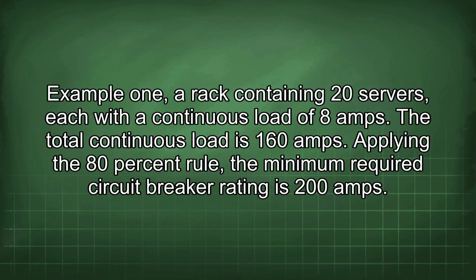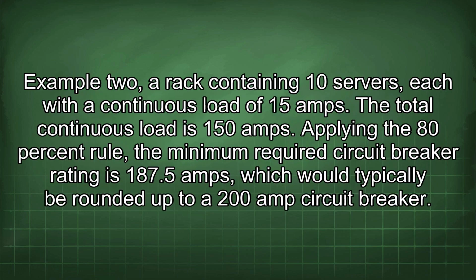Example 1. A rack containing 20 servers, each with a continuous load of 8 amps. The total continuous load is 160 amps. Applying the 80% rule, the minimum required circuit breaker rating is 200 amps. Example 2. A rack containing 10 servers, each with a continuous load of 15 amps. The total continuous load is 150 amps. Applying the 80% rule, the minimum required circuit breaker rating is 187.5 amps, which would typically be rounded up to a 200 amp circuit breaker.